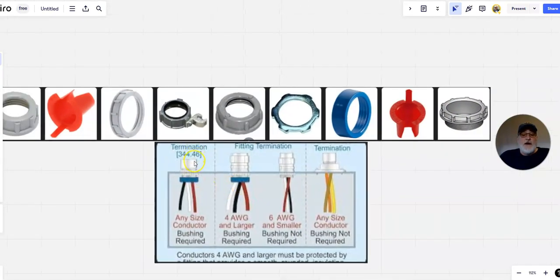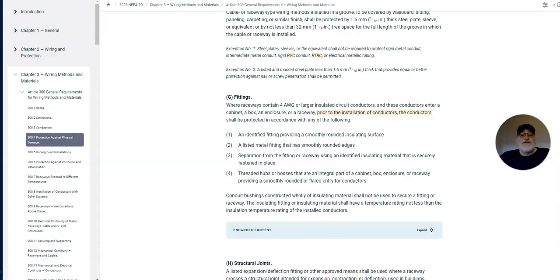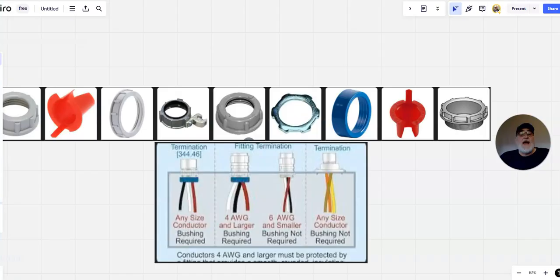Okay. These are some terminations. This is where they're talking about any conductor 4 or larger, the bushing is required. Number 6 and smaller is not required. In one of these types of termination points, a bushing is not required. That is one of those where they're referencing a threaded hub or boss that's integral to part of the cabinet. You'll find that basically right here on top of your meter bases. Okay.